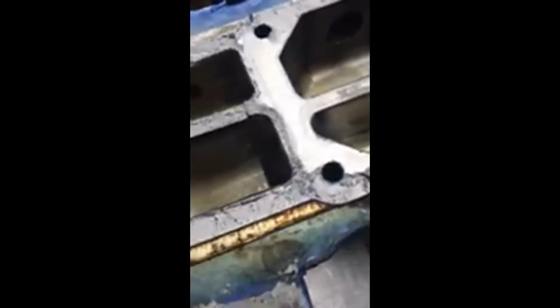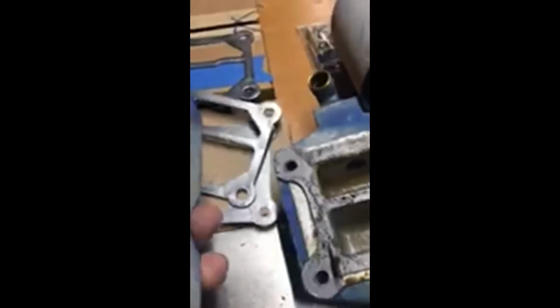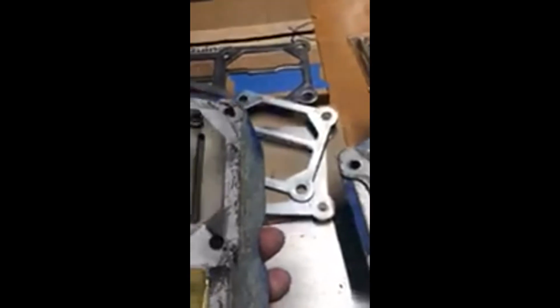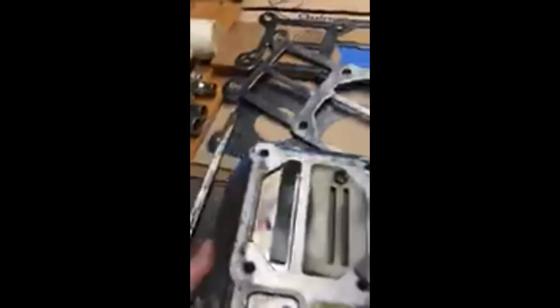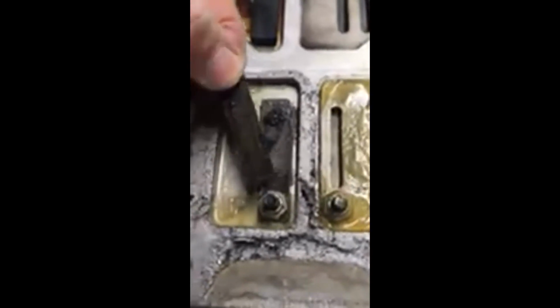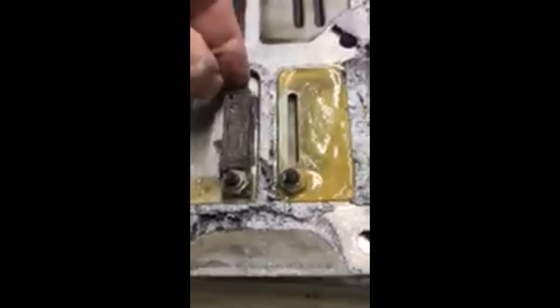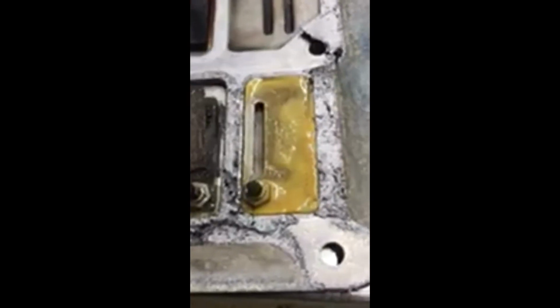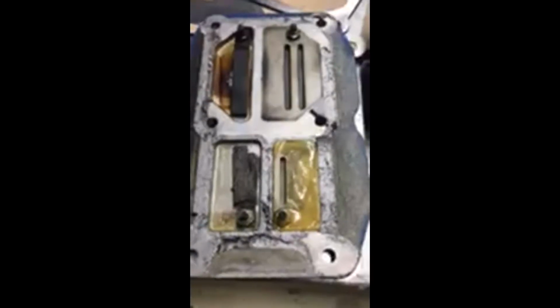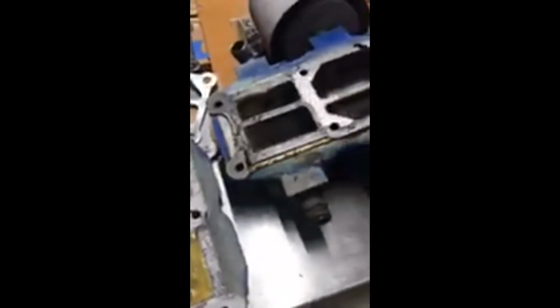And on first inspection, I don't see any signs of where we may be getting airflow. Although, look at that. That's a piece of one of the valves. It was just sitting loose there. So that's not right, for sure. Okay, the next step is to clean all the old gasket material off.